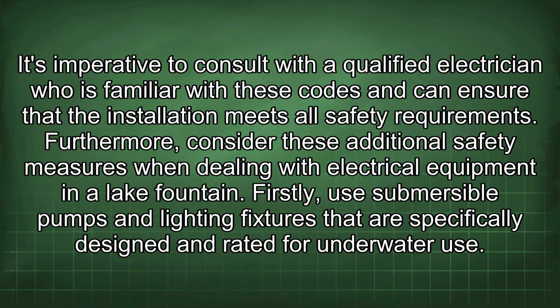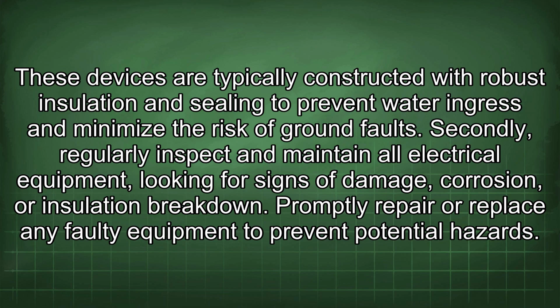Firstly, use submersible pumps and lighting fixtures that are specifically designed and rated for underwater use. These devices are typically constructed with robust insulation and sealing to prevent water ingress and minimize the risk of ground faults. Secondly, regularly inspect and maintain all electrical equipment, looking for signs of damage, corrosion, or insulation breakdown. Promptly repair or replace any faulty equipment to prevent potential hazards.